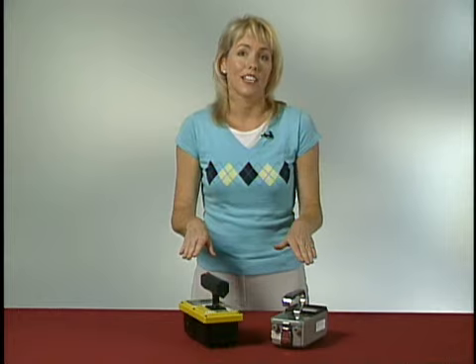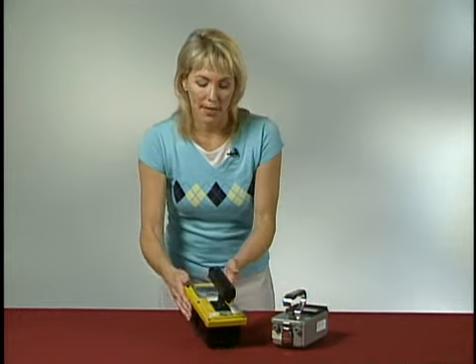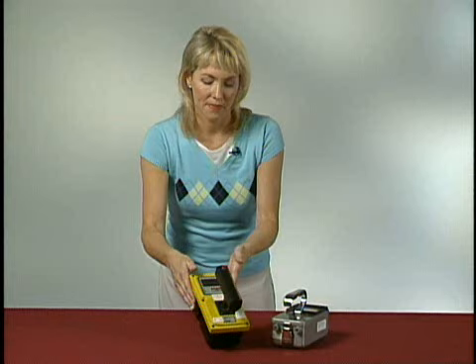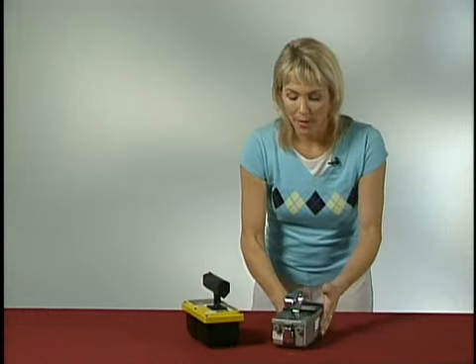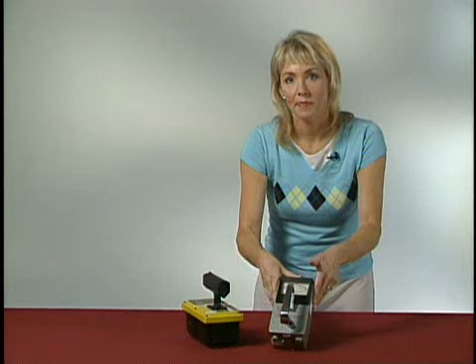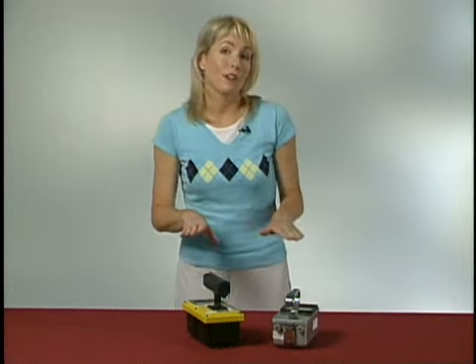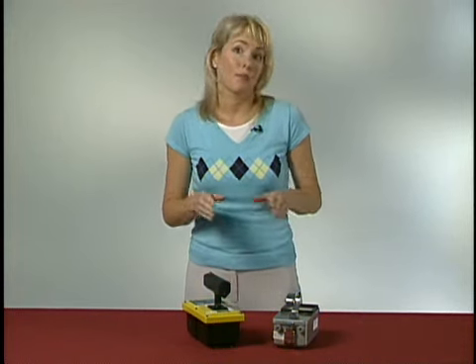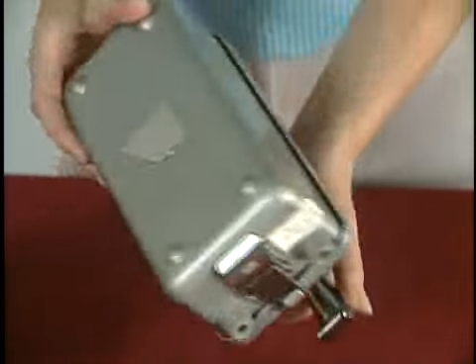Here are two different types of ionization chambers. One has a digital readout, and one has an analog readout. While these different ion chambers might not look the same on the outside, they all use the same type of detector on the inside, an air-filled cylinder approximately 3 inches in diameter. The primary role of ion chambers is to measure the radiation exposure rate due to gamma rays. Ion chambers are usually considered high-end instruments because they are used to measure high exposure rates, let's say 1 MR per hour and above. An ion chamber has a thin window that is protected by a removable cover.